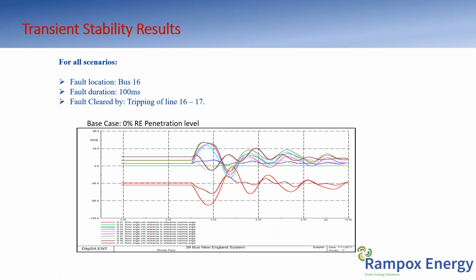This was the base case of the studies. These are the rotor angles of multiple generators. The fault was located at bus 16, just a random bus on the previous diagram, with a fault duration of 100 milliseconds, cleared by tripping a line. That's the base case.